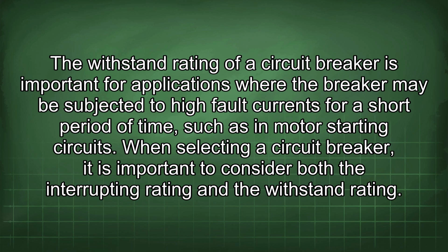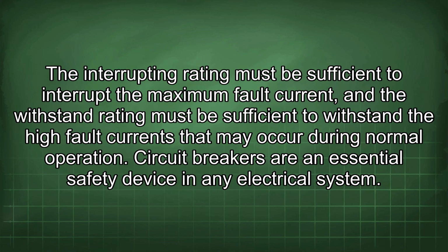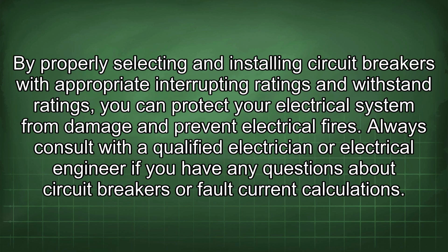When selecting a circuit breaker, it is important to consider both the interrupting rating and the withstand rating. The interrupting rating must be sufficient to interrupt the maximum fault current, and the withstand rating must be sufficient to withstand the high fault currents that may occur during normal operation. Circuit breakers are an essential safety device in any electrical system. By properly selecting and installing circuit breakers with appropriate interrupting ratings and withstand ratings, you can protect your electrical system from damage and prevent electrical fires.